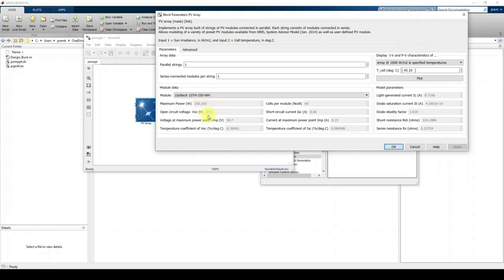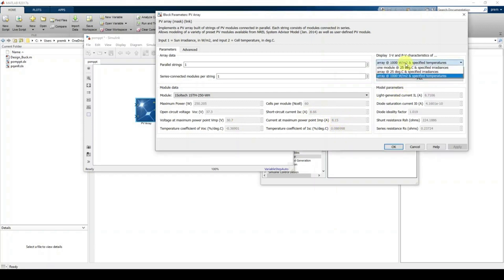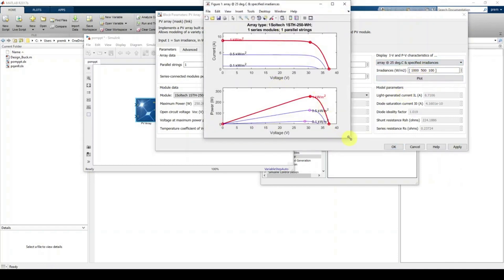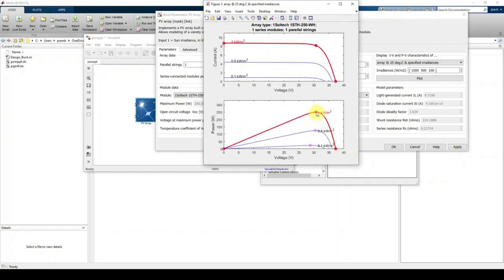You can also see the PV I-V curve. Select 'array at 25 degrees Celsius' with specific radiations and click Plot. Here you can see graphs for different radiation levels. For 1000 W/m², the maximum power is around 250.2 watts, and the voltage at the maximum power point is around 30.7 volts. For 500 W/m², the maximum power is 124.3 watts and voltage at MPP is 30.51 volts.